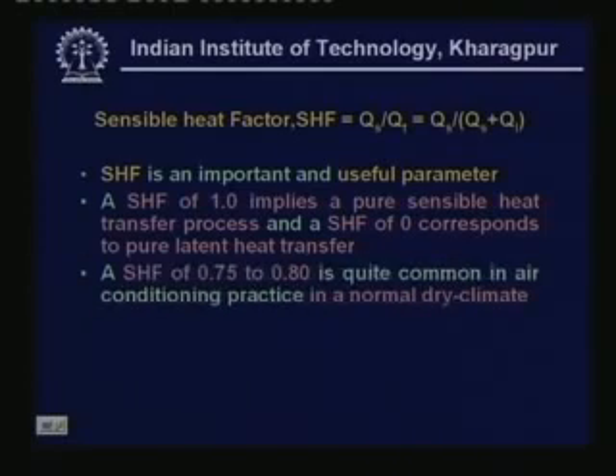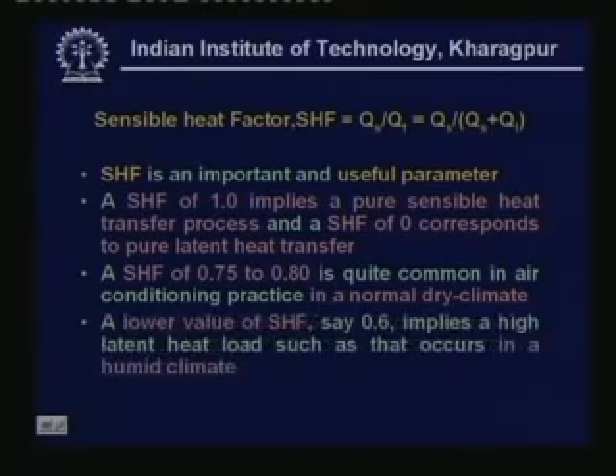An SHF of 0.75 to 0.8 is quite common in air conditioning practice in normal dry climate. In normal air conditioning systems, in normal dry climate, we find that the latent heat to sensible heat is in the ratio of about 1:4. That means you get a sensible heat factor of about 0.75 to 0.8. However, a lower value of sensible heat factor, for example 0.6, implies a high latent heat load such as that which occurs in a humid climate, for example in coastal regions. We shall use this factor later when we do the load calculations.